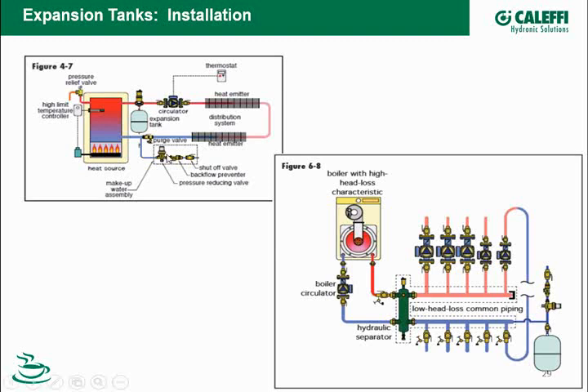Now, in figure 6.8, we're looking at a condensing boiler with a smaller mass to it. So I'm going to go into it as a primary-secondary connection with my hydraulic separator. Again, here's my hydraulic separator. All circulators are pumping away from that hydraulic separator.